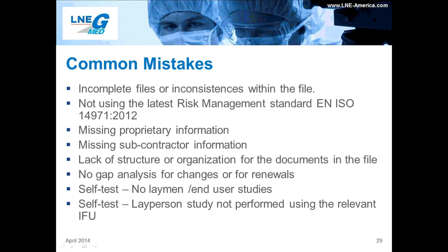No gap analysis for changes or renewals. When a change takes place, we don't necessarily have to re-review the whole file when an appropriate gap analysis is provided. However, unless the changes are highlighted, a full review is really the only way for us to assess those changes. The same with renewals. Over the course of 5 years validity of a design examination certificate, there should have been many changes and updates, so those should be summarized in your submission.